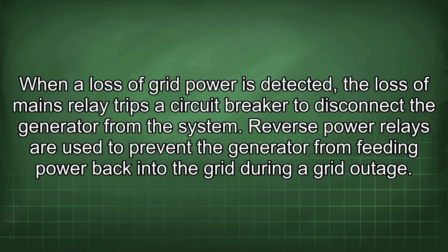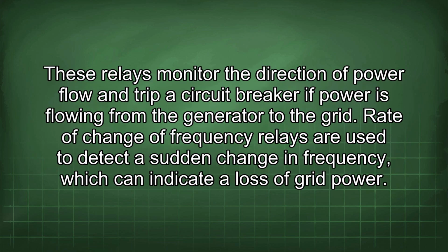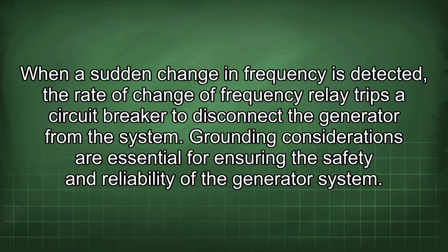Reverse power relays are used to prevent the generator from feeding power back into the grid during a grid outage. These relays monitor the direction of power flow and trip a circuit breaker if power is flowing from the generator to the grid. Rate of change of frequency relays are used to detect a sudden change in frequency, which can indicate a loss of grid power. When a sudden change in frequency is detected, the rate of change of frequency relay trips a circuit breaker to disconnect the generator from the system.